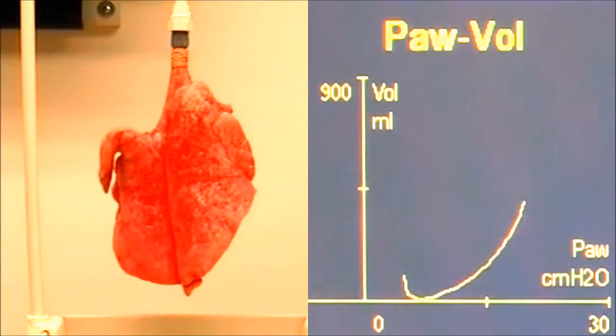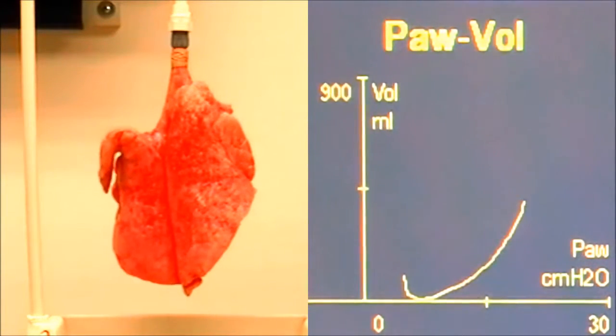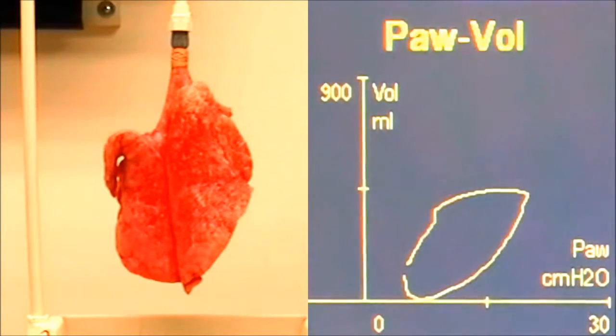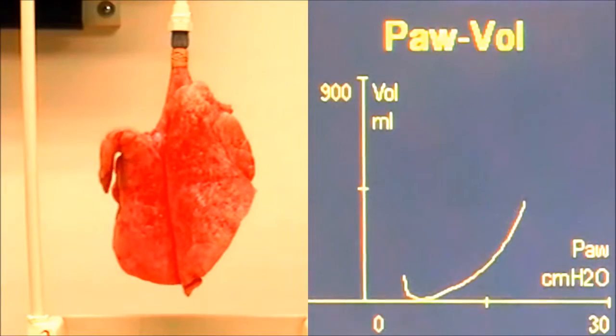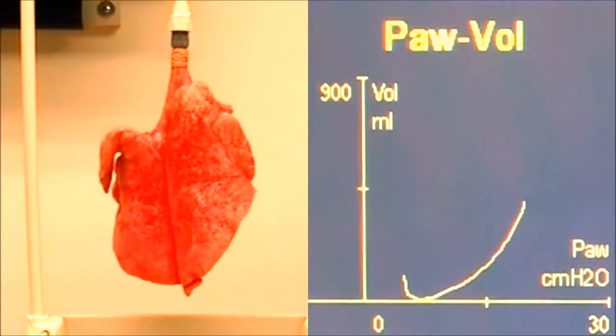The thing I want to point out is we're on 5 of PEEP right now. If I recruit and I go back to 5 of PEEP, my recruitment breath didn't really do anything because I'm going to need more PEEP than I have now to keep my lung open. So we'll demonstrate that.